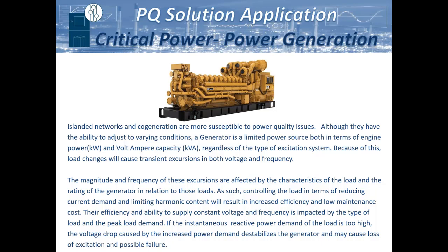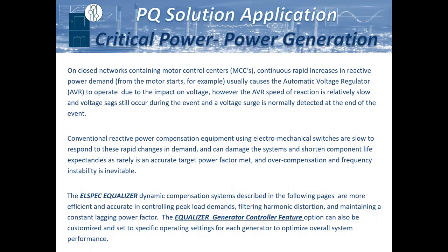So we have many customers in the Caribbean and island networks. Fiji Water is a very good example. They have about 38 equalizers throughout the Fiji Water plant in Fiji, and they won't add an additional production line without a system on it, because it had such a dramatic impact on their fuel efficiency being significantly improved, as well as their generator maintenance and repair costs being drastically reduced. Basically we've allowed the generator to work and perform what its purpose is, and not be influenced by all the loads on that network.